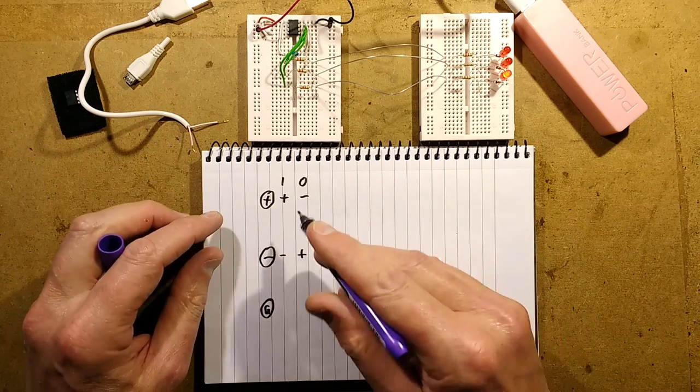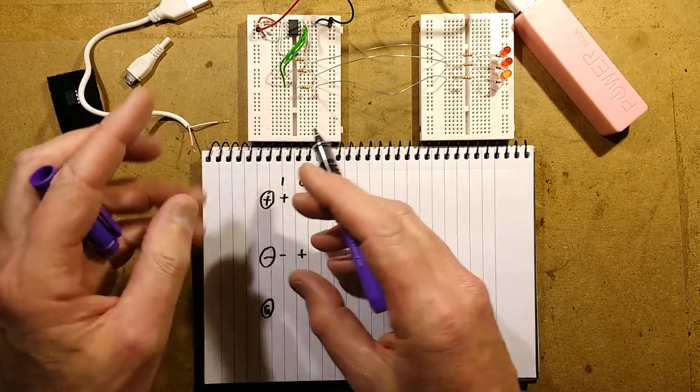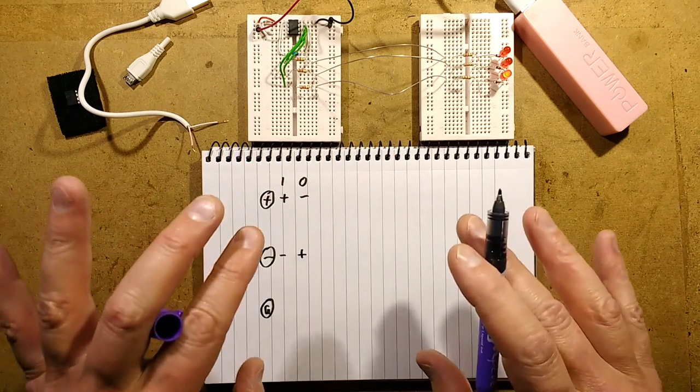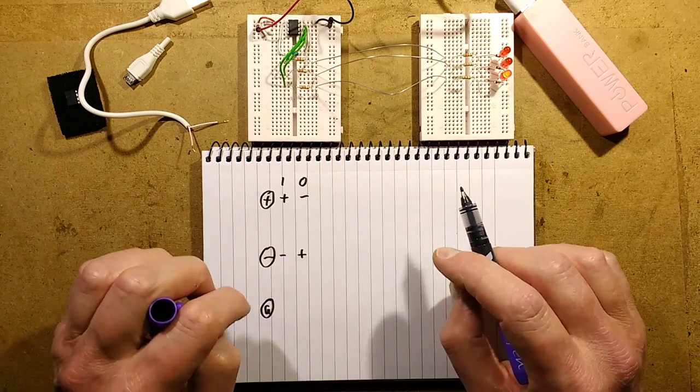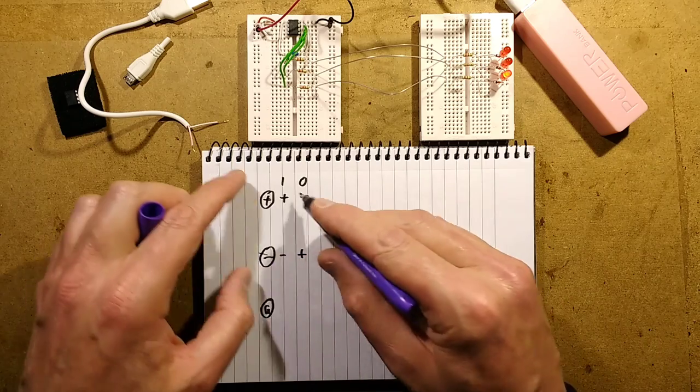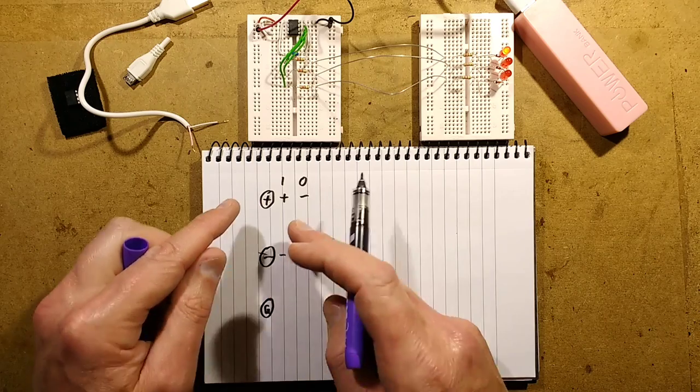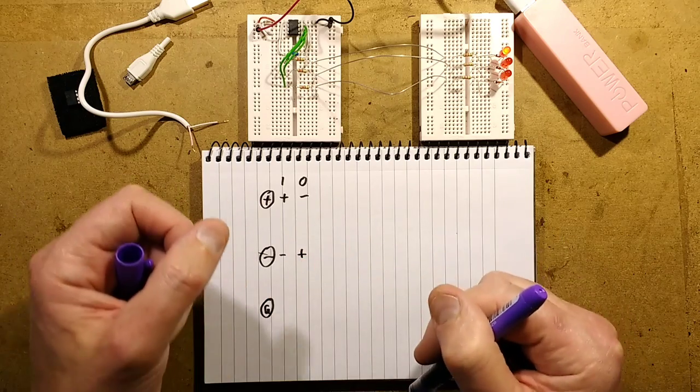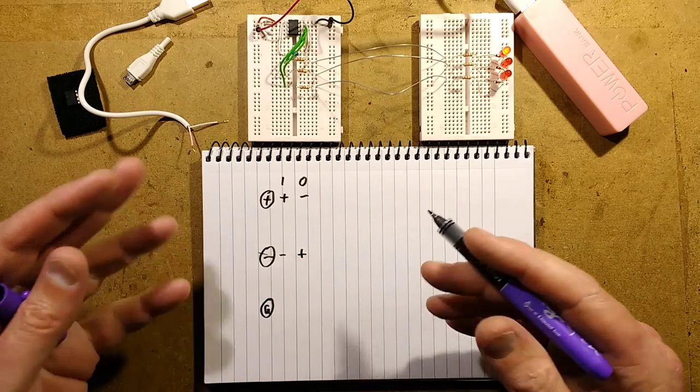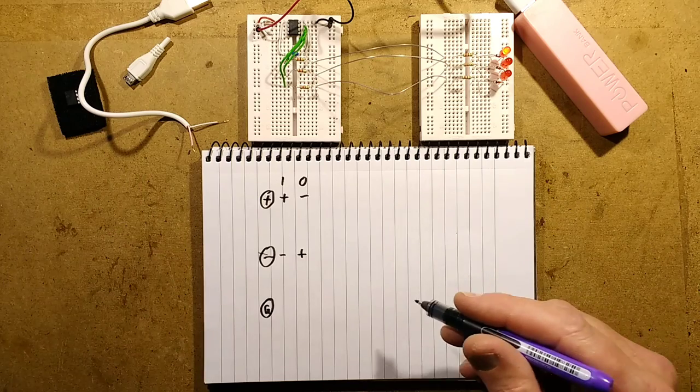And this, it's based on the RS485 standard. It means, because you're swapping polarity, it results in two things. If there's a net electrical field at these cables, if it's a modest run and they're picking up a common sort of electrical field common to both cores, it'll be cancelled out. It's looking for the difference between those two, the polarity between these two connections. And also, because it can push and pull at quite high current, it means that it can actually drive a very long run of cable.